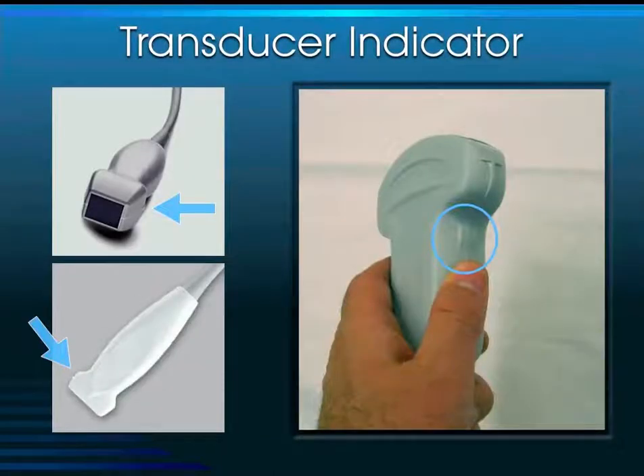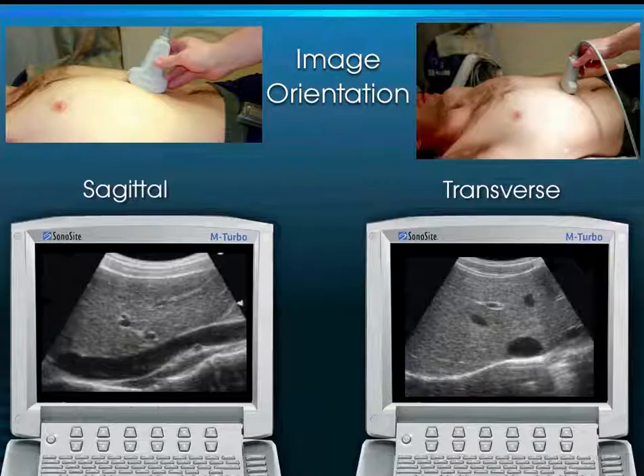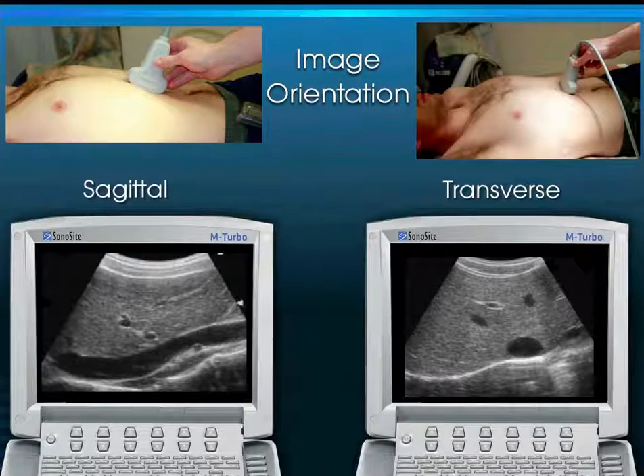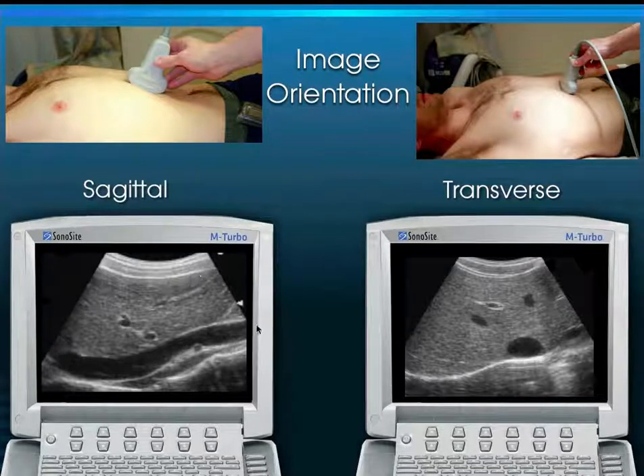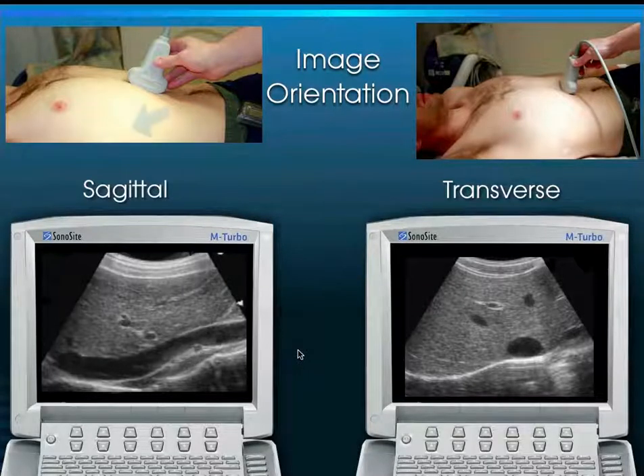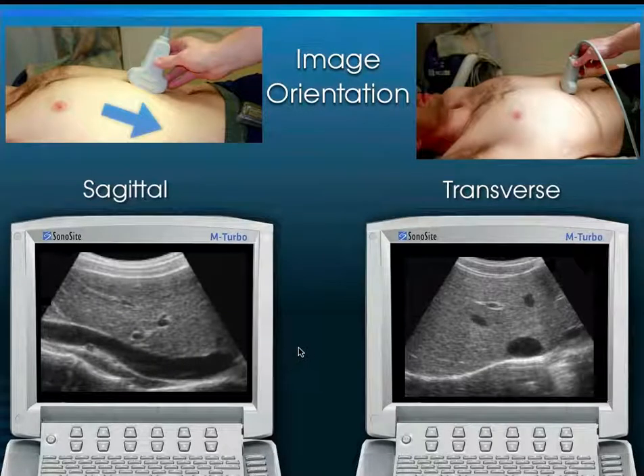Each transducer has an indicator on it. The indicator has a standard: in this country, it points towards the patient's head in a sagittal view, and towards the patient's right in a transverse view. Looking at this inferior vena cava in sagittal view, the head side is on the left of screen and feet on the right. If you accidentally aim the indicator down towards the feet, the IVC appears upside down.